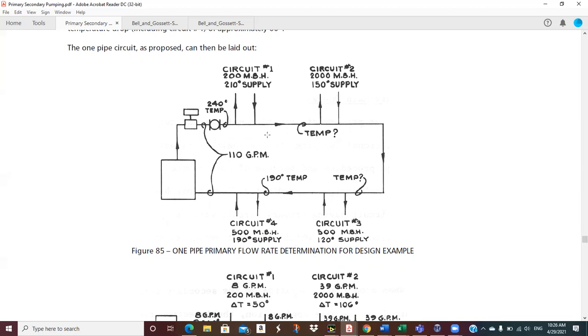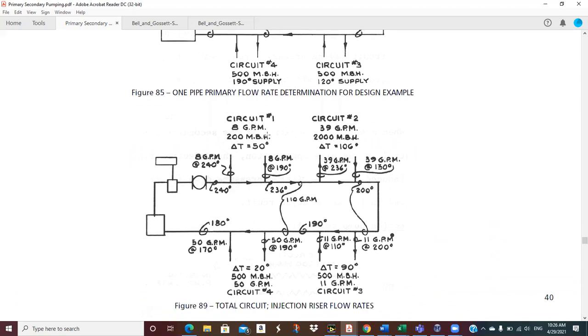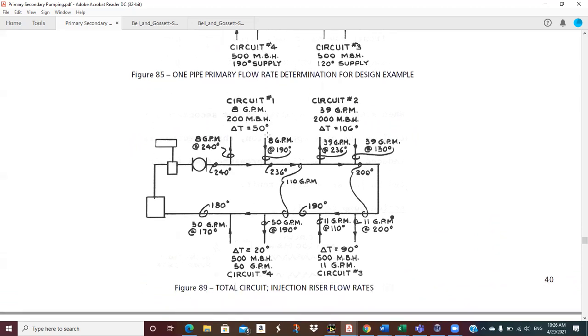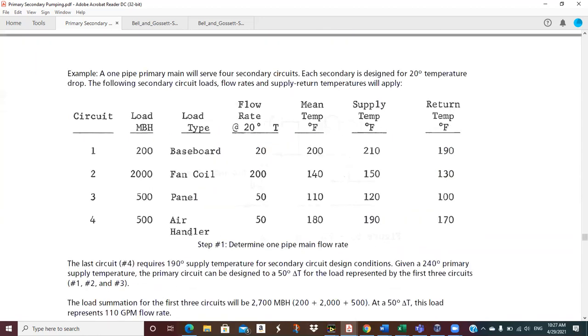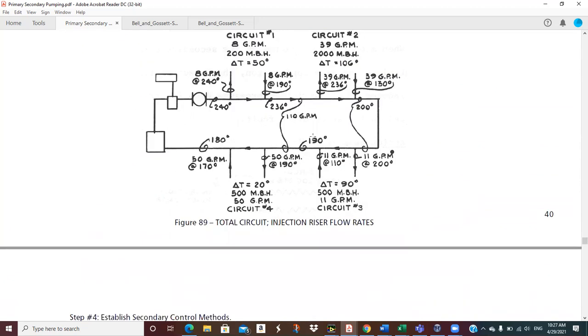If I was designing a system, I would not look at a one pipe primary unless I was somehow forced into it. So then he calculates, what's my primary water temperature as I go around the loop? I wind up over here, and the design parameter is that this last zone needs 190. He has to have enough temperature and flow, enough heat, that he can still have 190-degree water here, because that's what he has to pull into this circuit; that's the spec on the circuit. So supply temperature number 4 is 190, and he runs a calculation for the first 3 to make sure he still has 190-degree water here. Then it goes on from there.